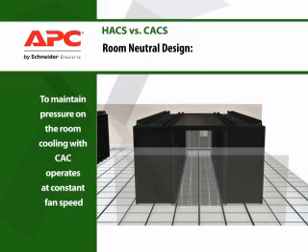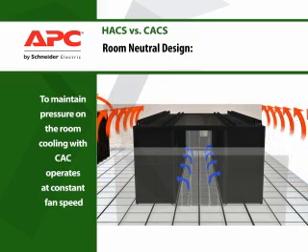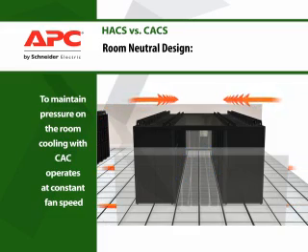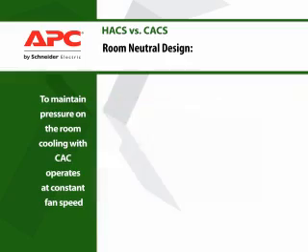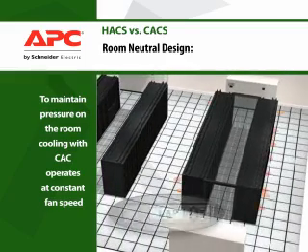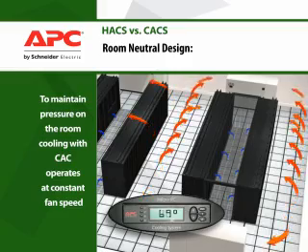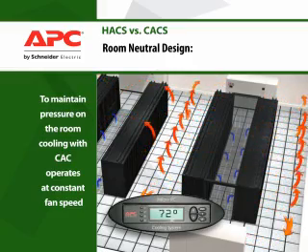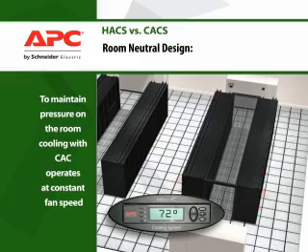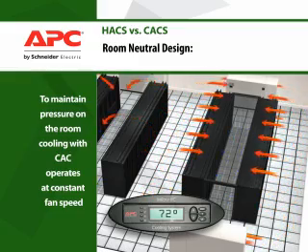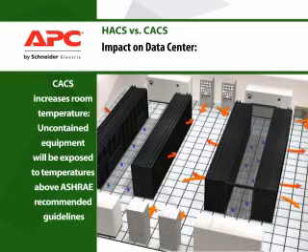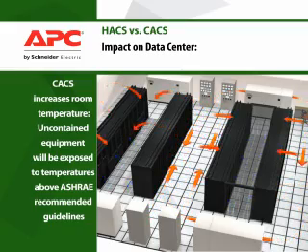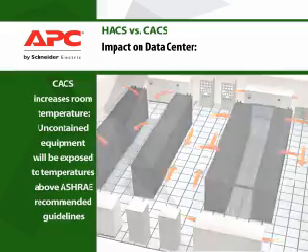The Cold Aisle Containment System is designed to isolate the cold aisle and allow the room temperature to increase, which in turn increases the return air temperature to the room cooling units. Because of floor leakage and other mixing that happens within a room cooling environment, the return air temperature cannot reach the same temperatures as in the HACS, resulting in less efficient operation of the cooling system. To improve efficiency in cold aisle containment, the temperature of the room must increase, which poses an issue for any equipment in the data center that is not contained, leaving non-rack equipment operating well above recommended temperatures.